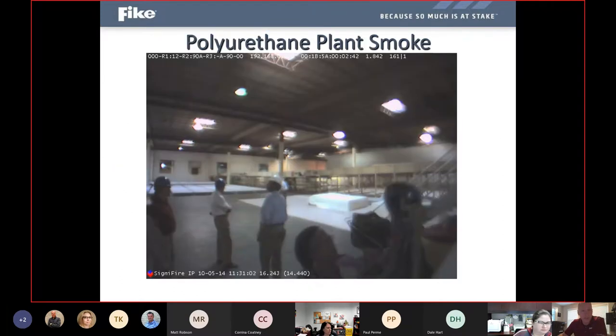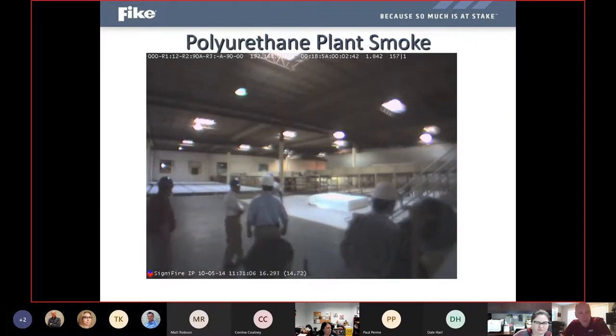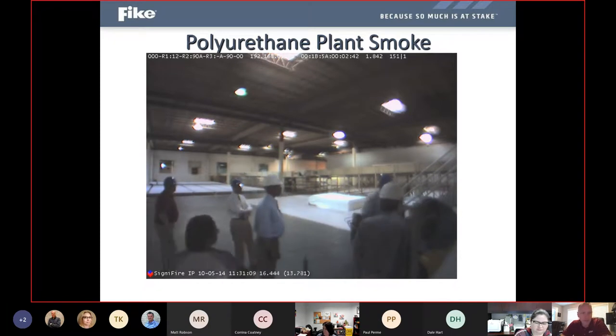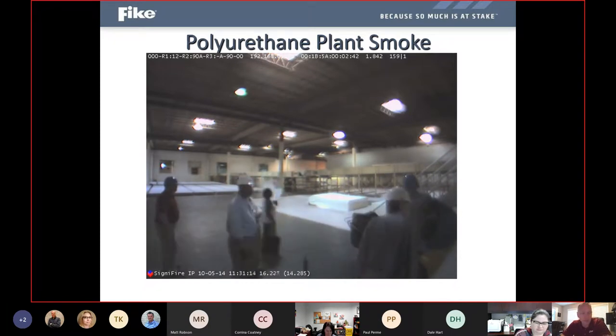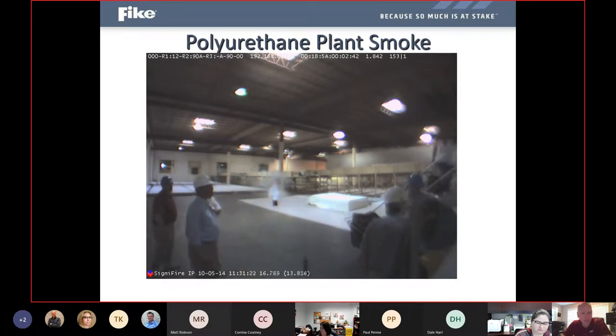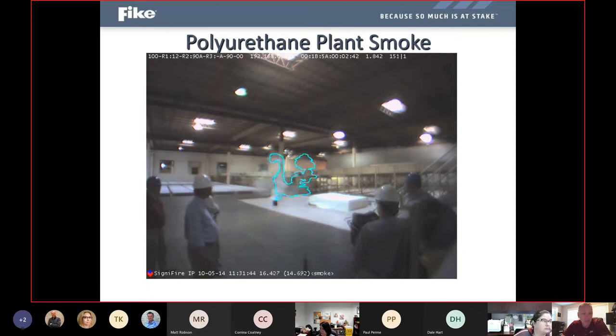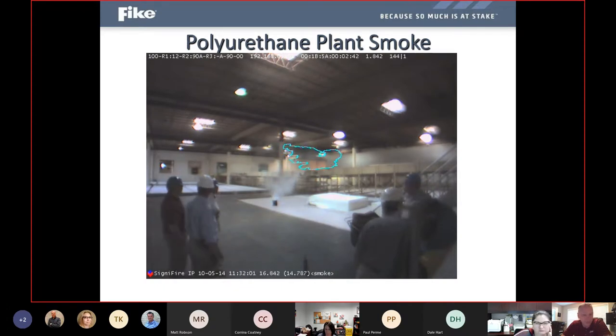So if we look at some examples as to how these cameras work, this is a smoke emitter test that was done in a plant. So you can see the smoke candle was lit in the bucket there. And in this case, I believe there was a 10 second delay programmed into the camera. So it wanted to consistently and constantly be detecting smoke for 10 seconds before it went into alarm. And you can see as that smoke continues to emanate there from the barrel, now the 10 seconds have lapsed and now the system has outlined that smoke cloud. And once that green outline appears there, that is the relays on the back of the camera triggering a response or an alarm signal to the building system.